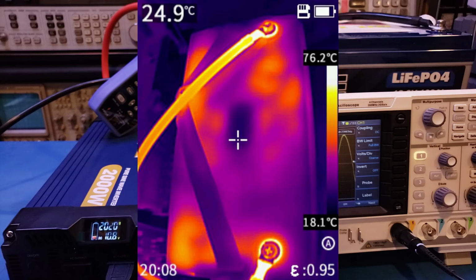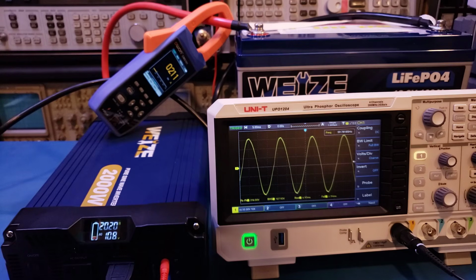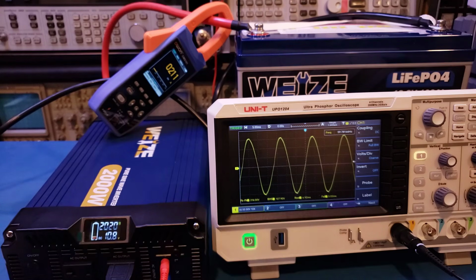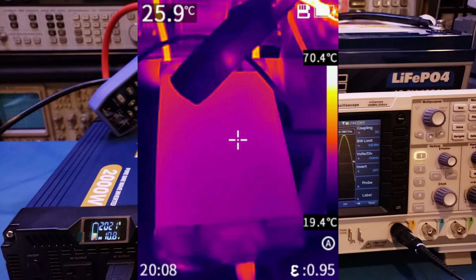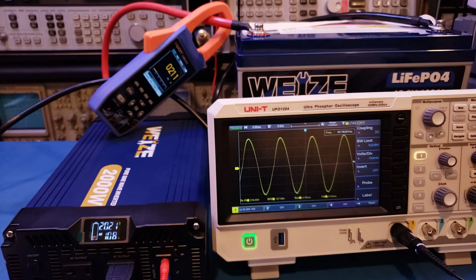You can see from the thermal image that the battery is getting pretty warm, so I assume if I keep running at this output, it will probably eventually cut off due to thermal limits. I took a few thermal images—here's the inverter, which is actually running quite cool. Keep in mind we're currently running at almost twice the maximum continuous rated current for the battery.